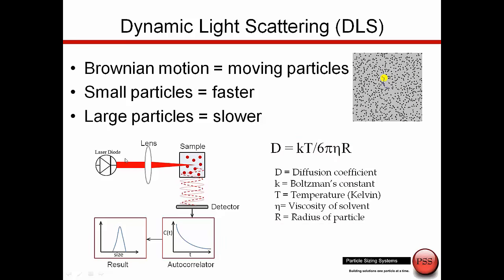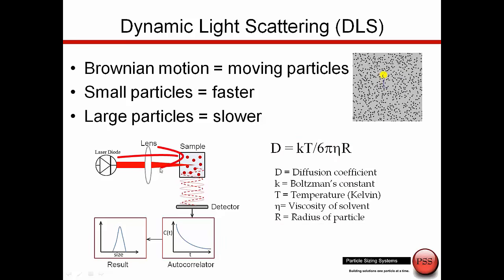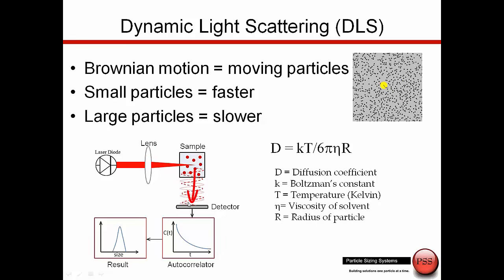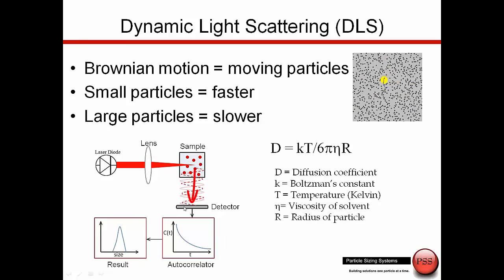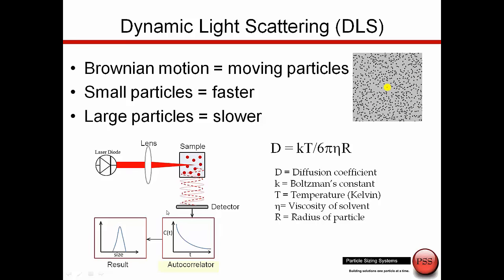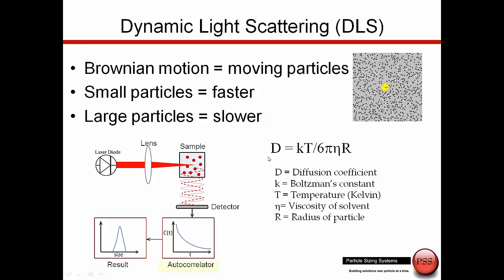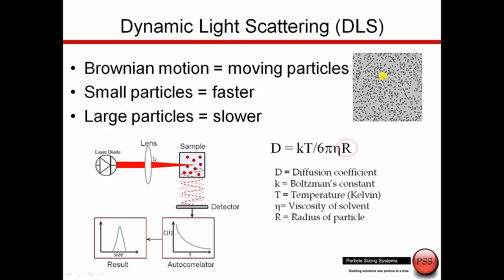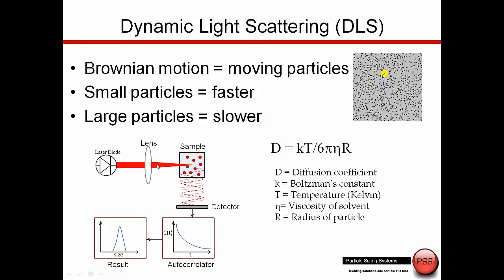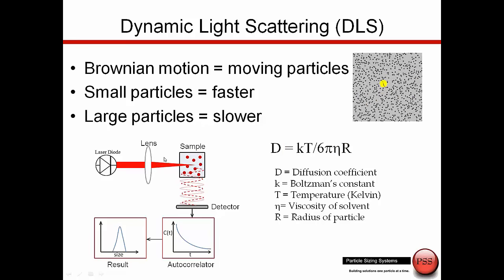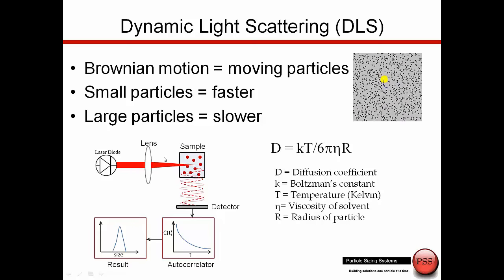The way we do the measurement is we have a light source. We then look at the light scattering from the detector, and as the particles move we get from the light scattering and build up this autocorrelation function. From this correlation function we determine the diffusion coefficient, and from the diffusion coefficient we calculate the particle size. That's how we determine particle size using dynamic light scattering, and most of these measurements are made in the laboratory, but today we'll be talking about how we can do this online.